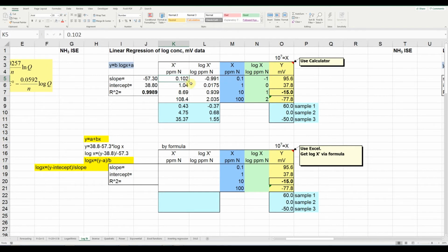So that's okay. But the next result, we had 1 ppm standard, we measured 104. So move the decimal over 2 places, that's plus 4 parts in 100, plus 4%. That's getting kind of high. That's not that great. Check out the 10 ppm standard. You measured 8.7. Ooh, that is terrible. If this was 100 ppm, this would be 87 ppm. You are 13% too low. That's terrible. And that's the reason why you should run regression while you're getting your samples, so you know right away.